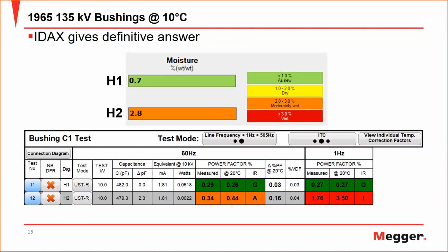I have another case study that I didn't show here, but it was RIP bushings. 9 were delivered. A handful had water inside the wooden crate and within the plastic, and 1 Hertz was used to confirm that there was moisture ingress into these bushings. So there are many reasons why a bushing would degrade, all the way from manufacturing through just normal service aged degradation.